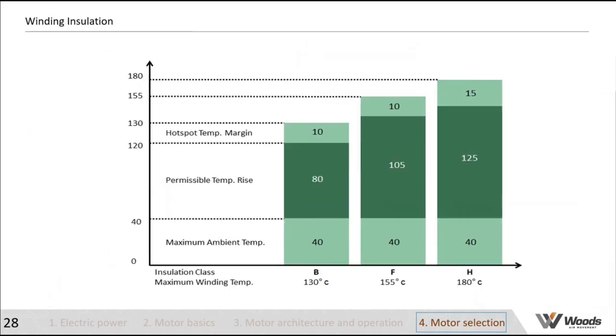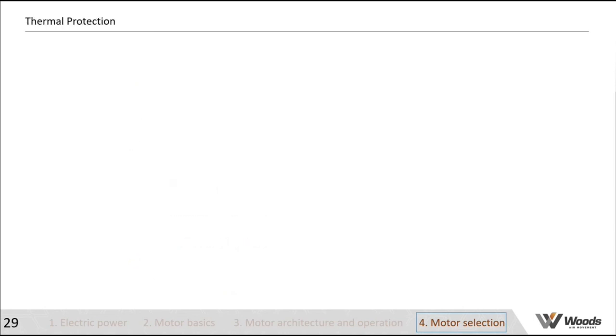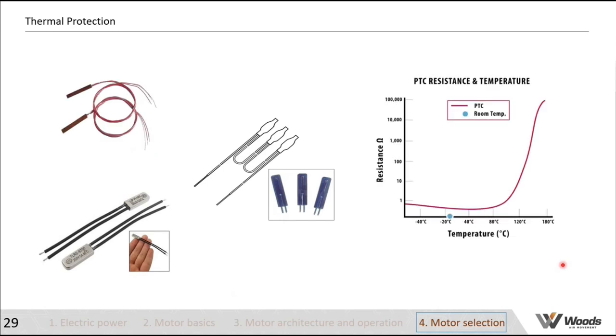Insulation class relates to the maximum winding temperature the motor can sustain. The further down the alphabet the class letter, the higher the maximum winding temperature — classes include A, B, F, H. For example, class H allows a higher maximum winding temperature than class F. Moving on to thermal protection: there are two types — thermostats and thermistors.